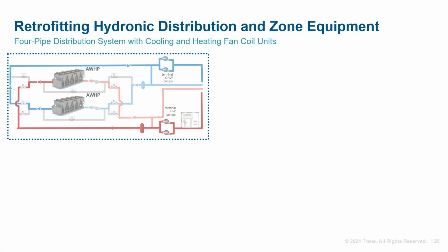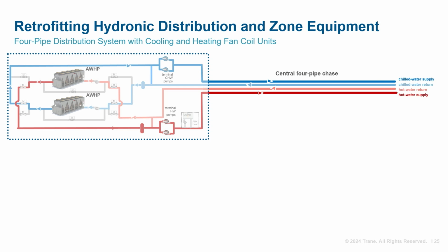Thank you, Sarah. So far, we have discussed retrofitting the central hydronic heating and cooling plant. However, this is only half the system. We are now going to look at the hydronic distribution and the zone heating and cooling units. The majority of the buildings that utilize hydronic heating and cooling systems are equipped with a 4-pipe distribution system. There is a central chase with very large pipes through the center of the building that distribute the water or glycol solution to and from the central plant. The 4 pipes are chilled water supply, chilled water return, and hot water supply and hot water return.